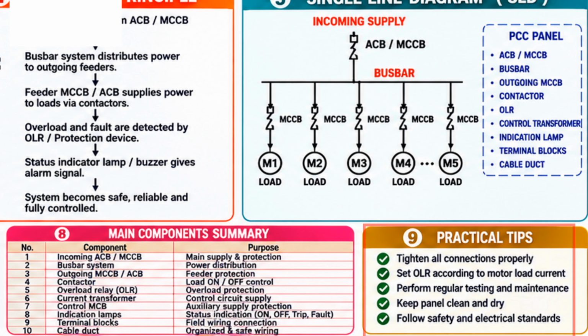Before opening a PCC, always make sure the panel is properly isolated and all safety procedures have been followed. Never rely only on the position of a circuit breaker. Always verify the absence of voltage using an approved test instrument. Regularly inspect bus bar joints, cable terminations, and ventilation openings. Thermal inspections can identify loose connections before they become dangerous. Remember, most electrical failures don't happen suddenly. They usually begin as small problems that are ignored over time.